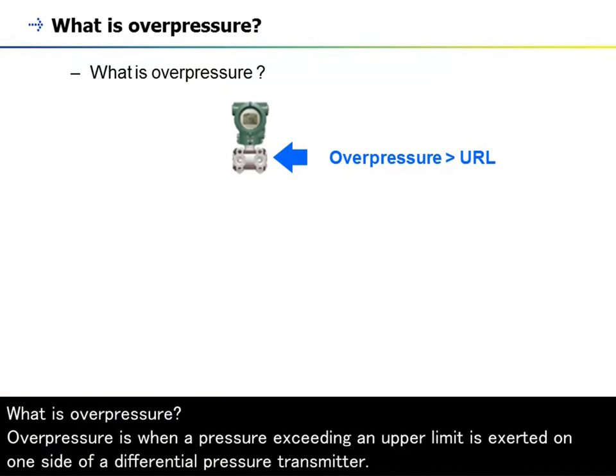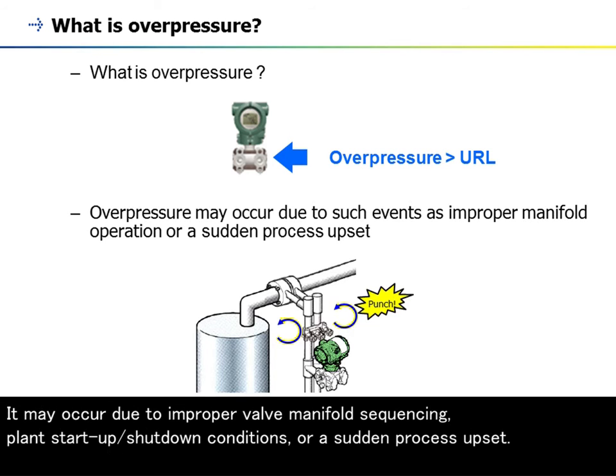What is overpressure? Overpressure is when a pressure exceeding an upper limit is exerted on one side of a differential pressure transmitter. It may occur due to improper valve manifold sequencing, plant start-up or shut-down conditions, or a sudden process upset.